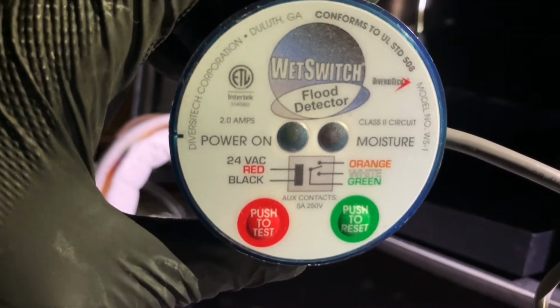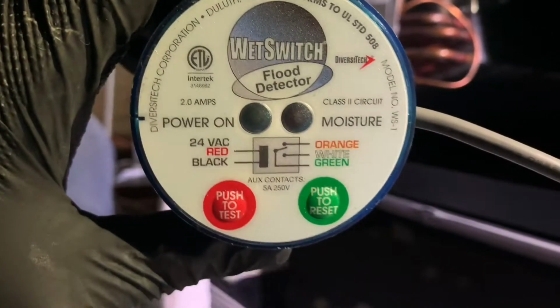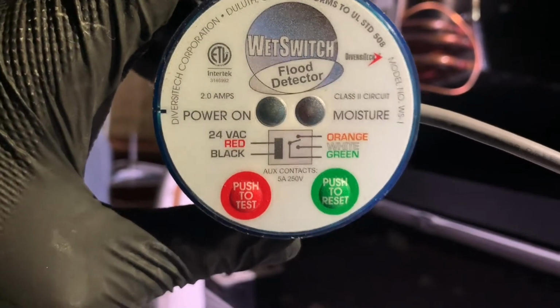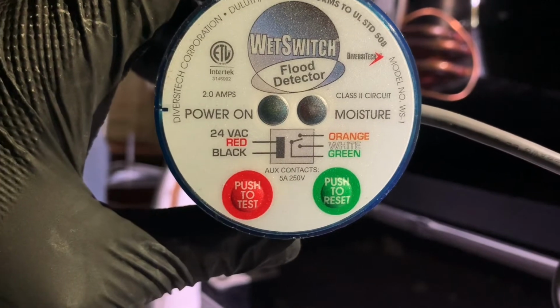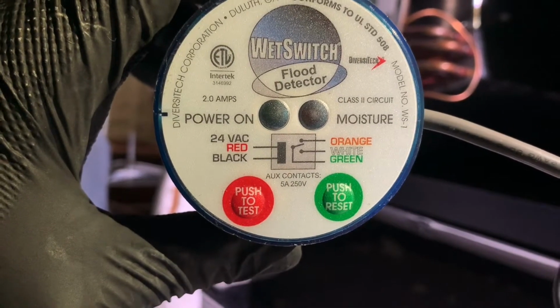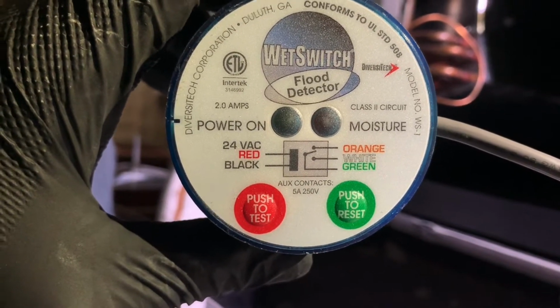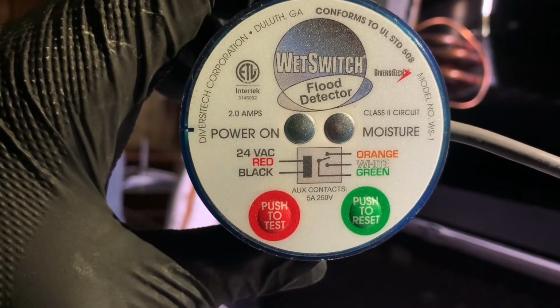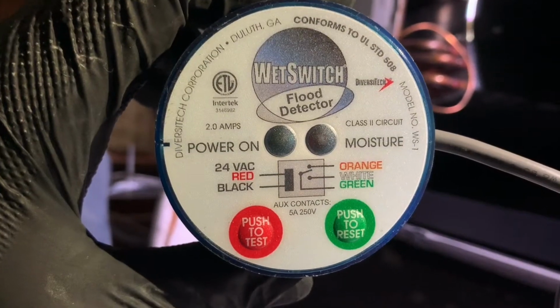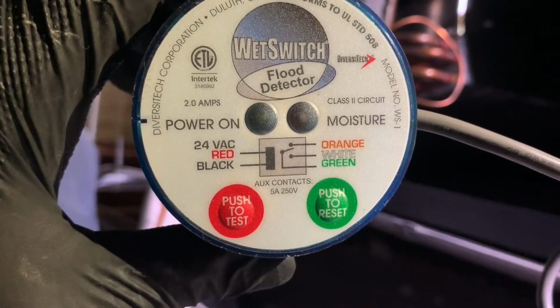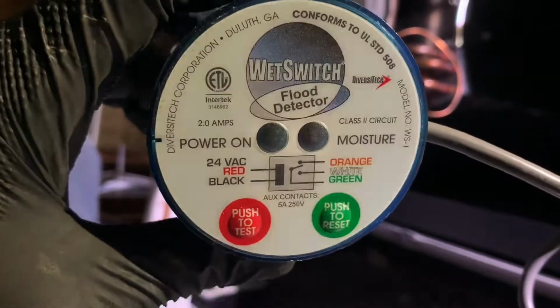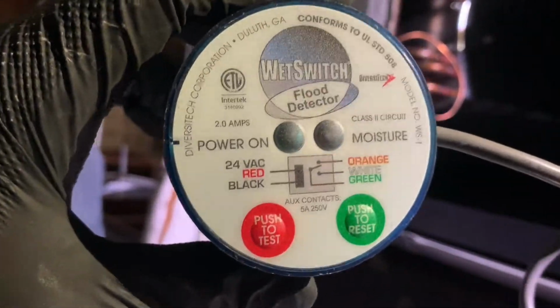Is a flood detector. Okay, so the green wire is coming off of this flood detector, and the orange wire and this flood detector, I connect that to the 24 volts hot, 24 volts leaving the transformer. So in other words, if this thing senses a flood or water, thermostat, the whole system goes down. No cooling, no fan, thermostat goes blank, so on and so forth. No heating, nothing. Okay, so back to where I left off.